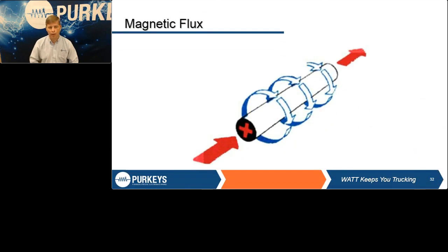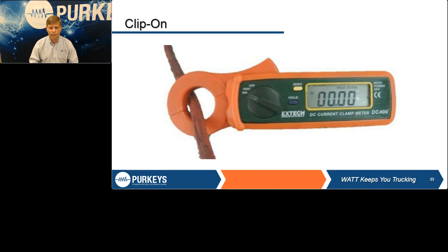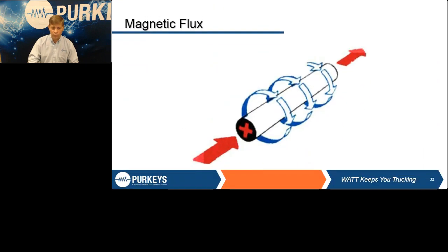The next type of ammeter we're going to talk about is actually a separate piece of meter, or it may be an add-on for a multimeter, but instead of an inline or shunt type ammeter, it is an inductive or clip-on ammeter. They all have different looks, different size jaws, different ranges, everything. But the beauty of this type of meter is you don't have to break the circuit. All you're going to do is open up the jaws, put it around that cable, and it will be able to read that magnetic flow and show you exactly how much current.